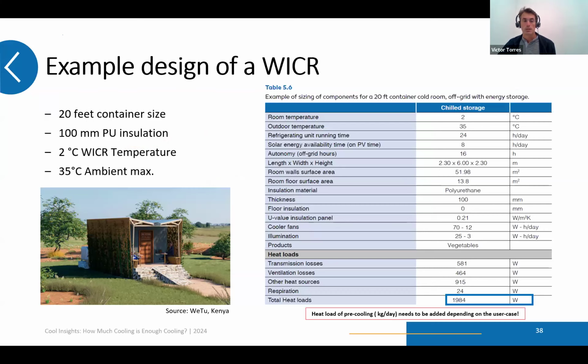The cold room temperature is 2 degrees, and we're designing this cold room for a maximum ambient temperature of 35 degrees. This brings me back to the concept Jeremy introduced of the design day: you need a design day as an average of what you're designing for, based on a typical climate day and a typical cooling scenario with a certain amount of products.